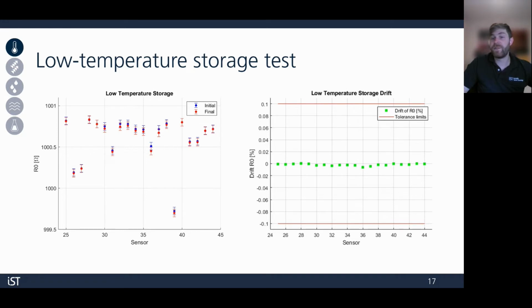Next, we look at the drift after storage at a low temperature. So this is sometimes an important factor when you're working in a space application. You'll be dealing with pretty low temperatures. In our case, we're always looking to rate these sensors down to negative 200 C. So here the sensors are kept in liquid nitrogen, so negative 196 C for 168 hours. Then a 2-bath measurement is performed, like with all the other tests. And again, we observe barely any drift.